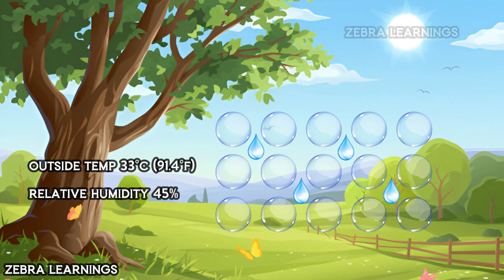Let's say the outside temperature is 33 degrees Celsius and the relative humidity is 45%. In this case, the dew point temperature is 19.5 degrees Celsius. Therefore, when the outside air temperature is 33 degrees Celsius and the relative humidity is 45%, the corresponding dew point temperature is 19.5 degrees Celsius.